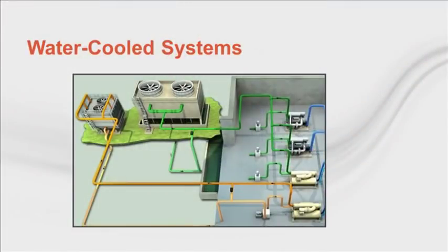Now let's turn our attention to the condenser or heat rejection side of the chilled water system. There are two main options, water-cooled and air-cooled. Here you see your basic water-cooled chiller plant. We have condenser pumps, valves, and cooling towers connected to the chiller's condensers. It's generally true that water-cooled systems are more energy efficient than air-cooled systems, especially when optimized in design. This is because they operate against the wet bulb temperature, which is lower than the dry bulb temperature that air-cooled chillers operate against. There also is a phase change, the latent heat of evaporation that is removed from the condensing circuit of a water-cooled system.